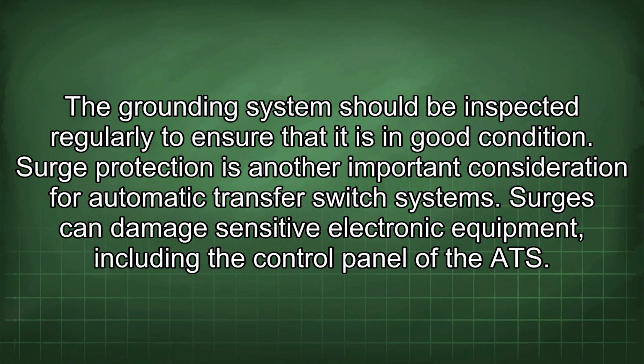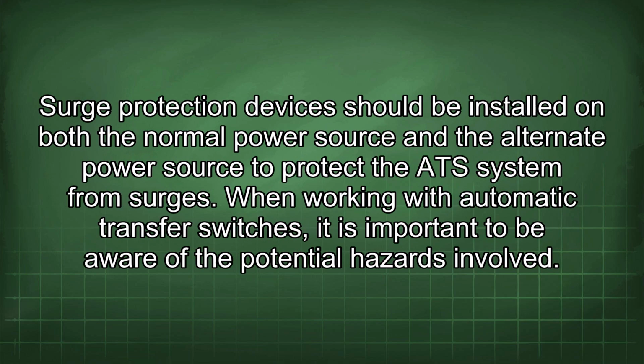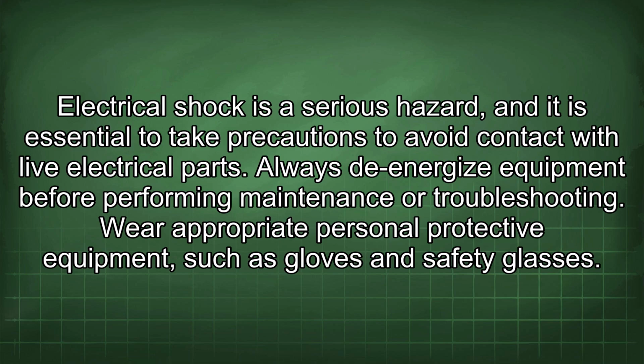Surge protection is another important consideration for automatic transfer switch systems. Surges can damage sensitive electronic equipment, including the control panel of the ATS. Surge protection devices should be installed on both the normal power source and the alternate power source to protect the ATS system from surges. When working with automatic transfer switches, it is important to be aware of the potential hazards involved. Electrical shock is a serious hazard, and it is essential to take precautions to avoid contact with live electrical parts.